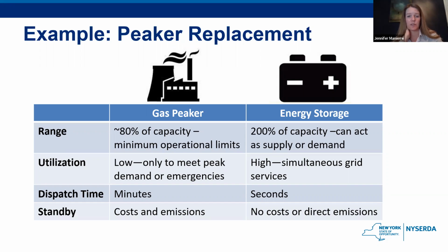They have typically been natural gas. And while natural gas is decent at that, it has emissions, and batteries actually can do the job better. So a gas peaker plant might be functioning at like 80% of its capacity, and it has minimum operational limits, right? Energy storage, on the other hand, batteries, not 80% capacity. You can think of them as having the capability of 200% capacity, because not only can they serve the function like the gas peaker does of pushing energy into the grid at those times of peak demand when it's needed, but they also have the capability of pulling excess energy off the grid when you don't need it. So that's how we look at it, as having a 200% capacity.